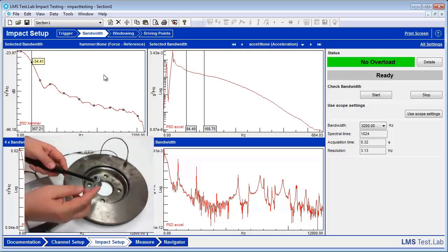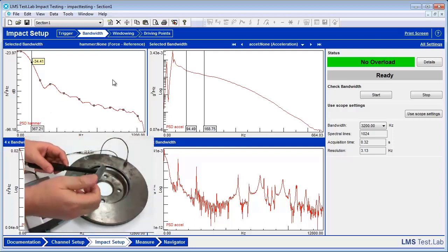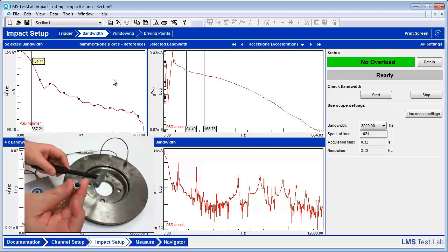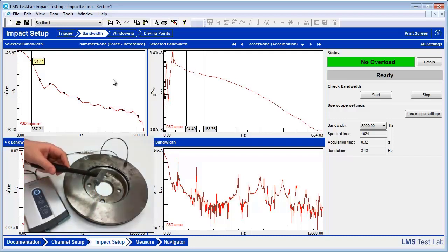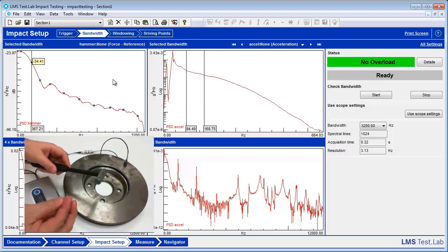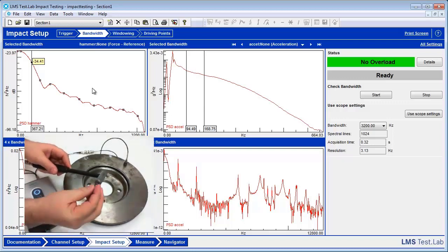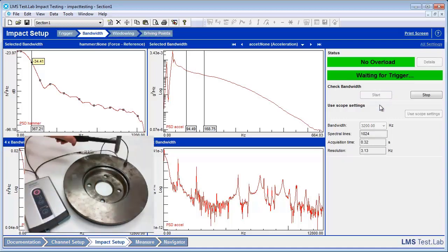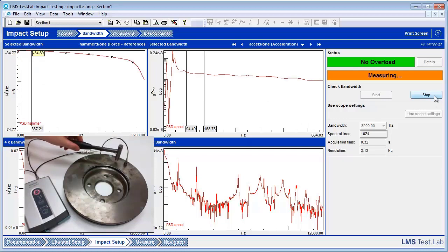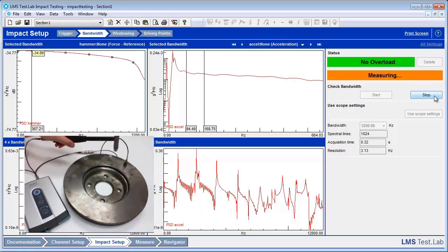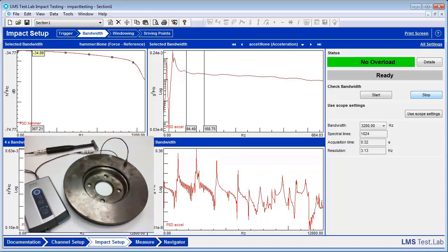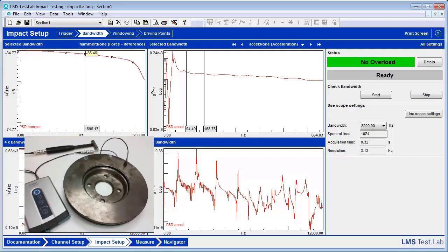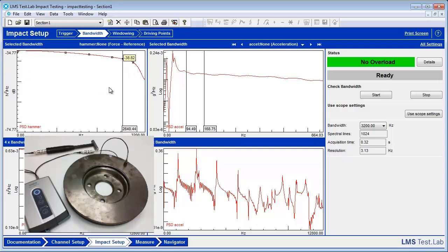So the first thing we can do to try to fix this is switch out our hammer tip. Right now we have a rubber tip on our hammer, which is a very soft tip. So we're going to try to switch that out for a metal tip, and we're going to start our check bandwidth again. And as we can see, we get a much flatter signal across our whole frequency range of interest. And we are well within a drop-off range of about 6 dB. So that's good.